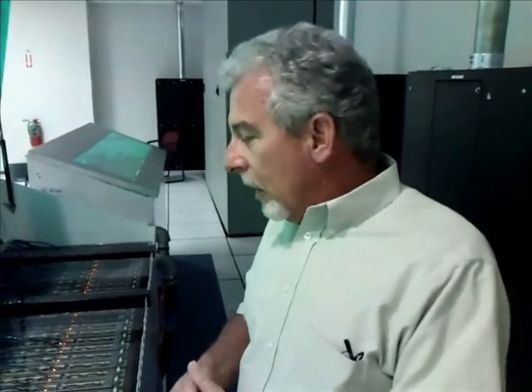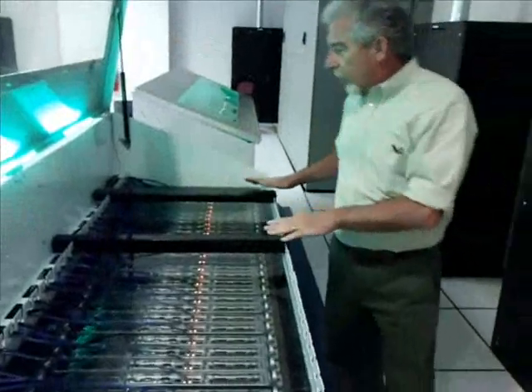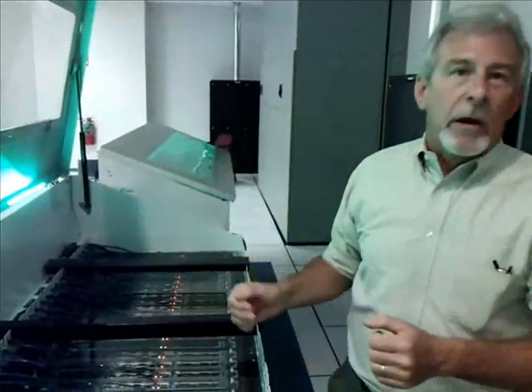These are conventional air servers. What we have to do is remove the fans, and also remove any thermal transfer material — generally a paste between the heat sink and the CPU itself — and replace that with a heat-transferable foil that still allows for good conductivity. The servers are then placed in as they are. We use 1U mainly due to weight. For maintenance, we have hooks on the side. A server is brought out and laid on a black bar, work is performed and components replaced, then it's set back down into the liquid cooling.